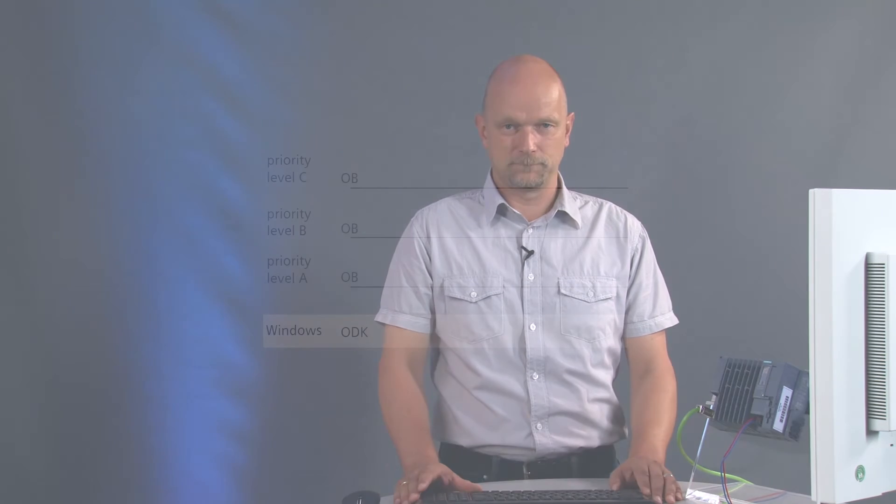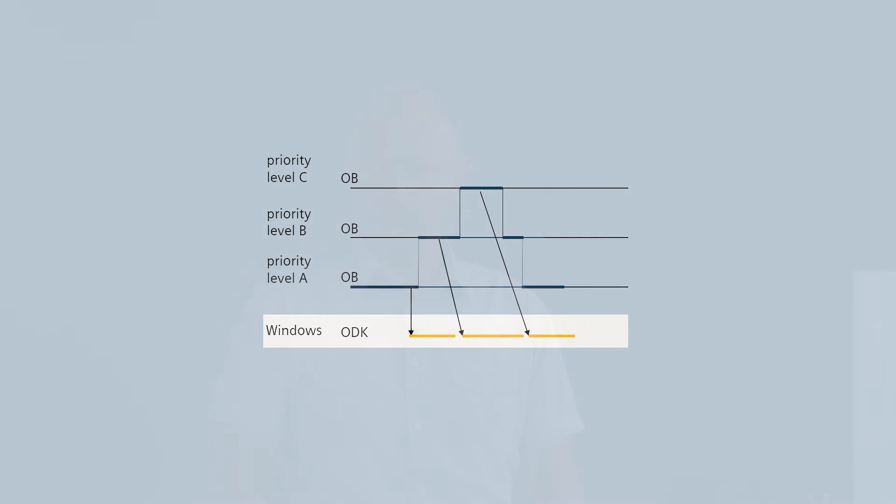We will look at what this means in a flow diagram. Each function is executed in one single thread. Each thread has the same priority, and the coordination is managed by Windows. We have no possibility to influence the priority from the controller side. That is why it is also not possible to interrupt a function that is already running by means of another function. The other function cannot begin until the original function has been properly completed.